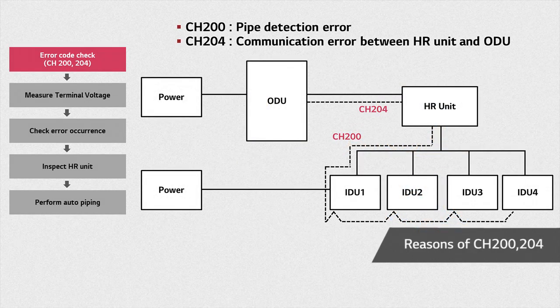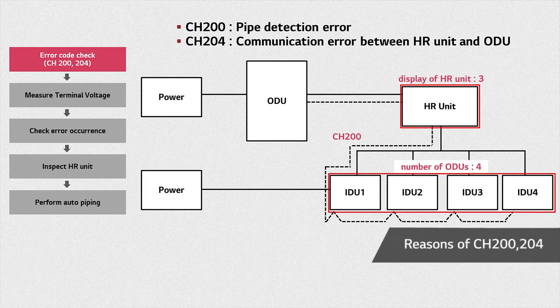While CH200 is a piping detection error, CH204 refers to a communication error between the HR unit and the ODU. Error CH200 occurs when, after auto-piping, the number of indoor units detected is different from the number of communicating indoor units. This miscount occurs mainly when the DIP switch setting has been wrongly done. Another reason is failure in the HR unit's communication cable and power cable, or a malfunction in the HR unit's PCB.